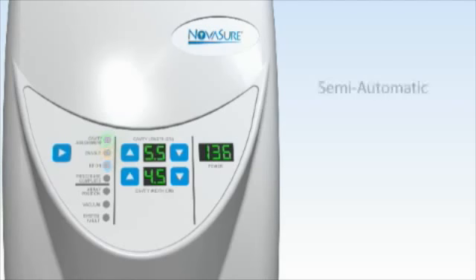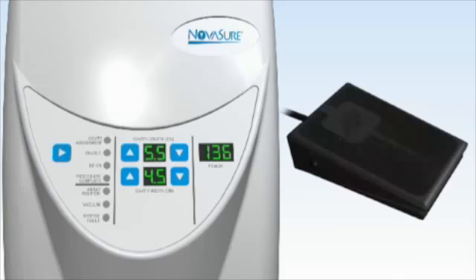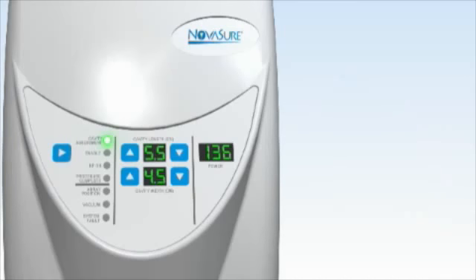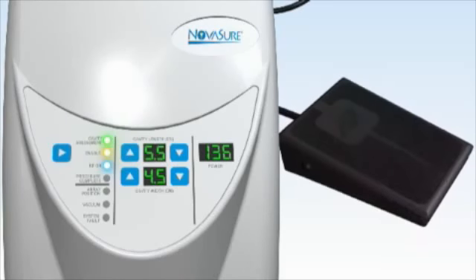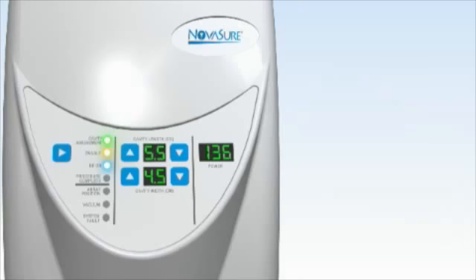To operate the system in the semi-automatic mode, do not press the Enable button prior to beginning the cavity integrity test. Begin the cavity integrity assessment procedure by stepping on the foot pedal once. Upon successful completion of the cavity integrity assessment, indicated by a steady green light, press the Enable button. The ablation will not start until the physician depresses the foot pedal again. During the ablation cycle, a blue RF on LED will illuminate on the front of the controller. Completion of the procedure is indicated by a green Procedure Complete LED on the front of the NovaSure RF controller.